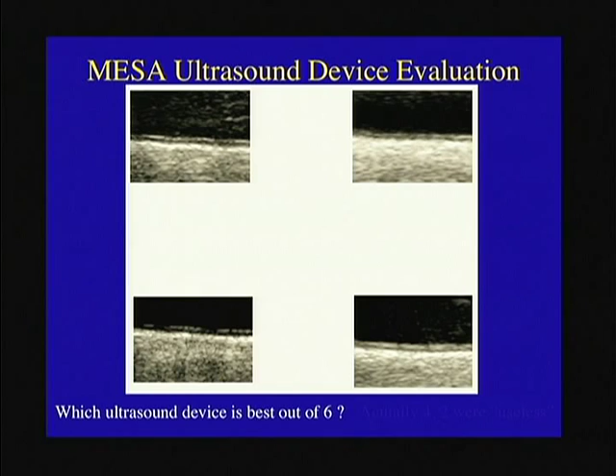Now, does someone see something wrong with this slide? I said 6, right? How many images are there? 4. You're going to say, why are there 4 images? Well, the truth is, 2 of the image sets were so poor, it was not worth even trying. You couldn't see the interfaces properly. So of the 4, we sent this survey, and ultimately we got one machine that performed better, more consistently, and that's what we picked. There was no bias, no commercial influence. If someone tells me that manufacturer X has a better machine for this, I don't listen to them, we just measure them. By the way, this is the second time we did this.